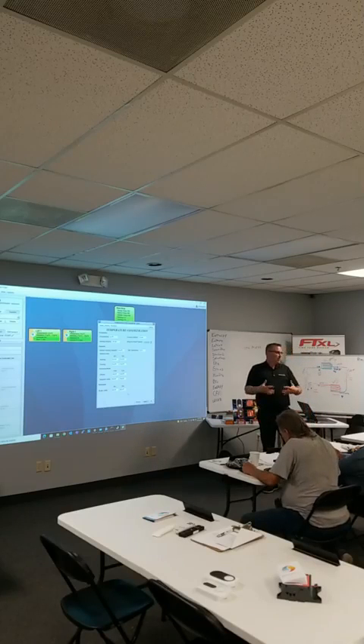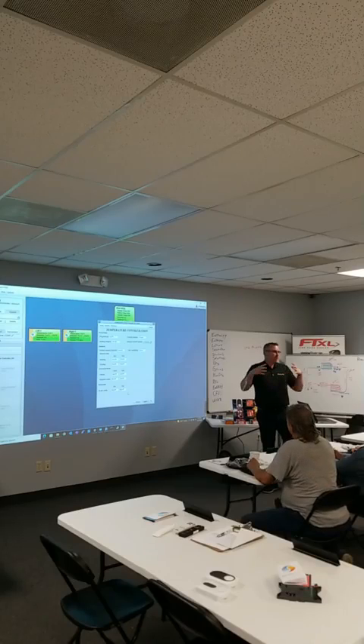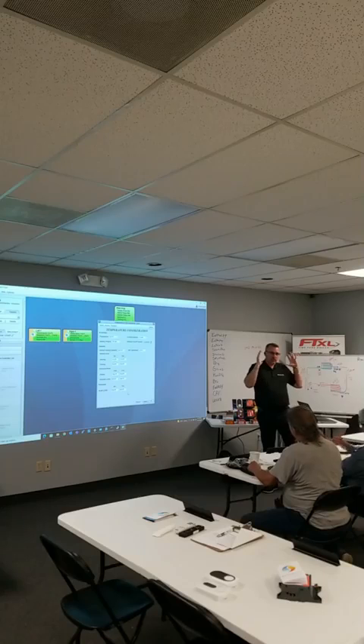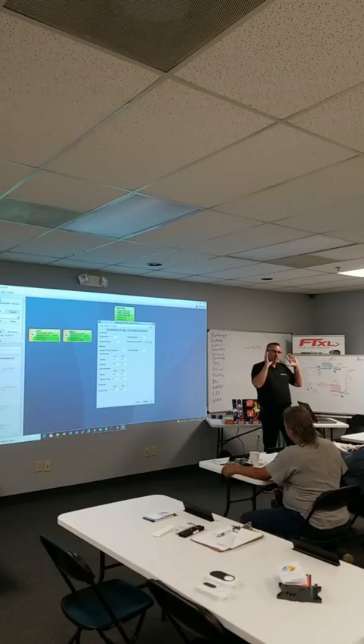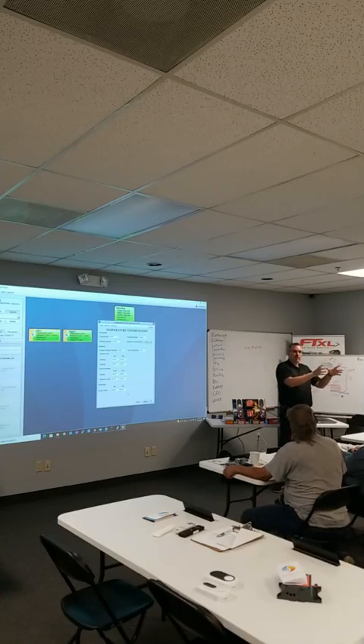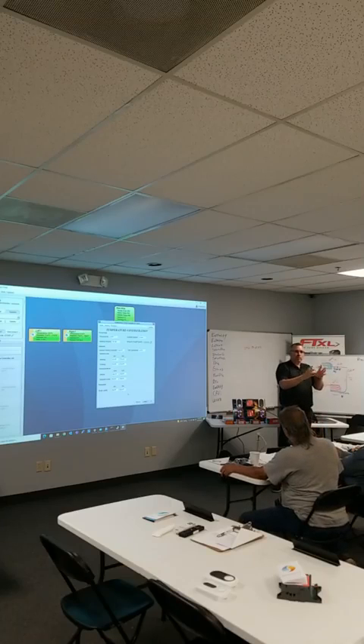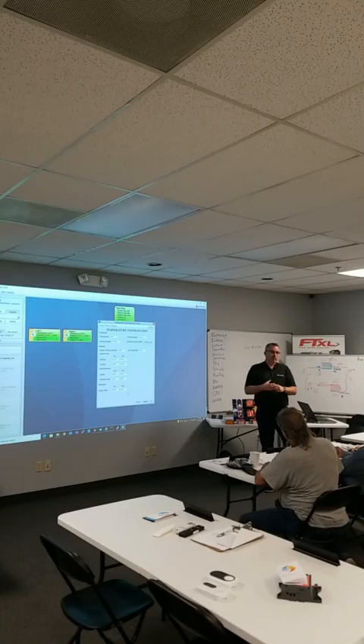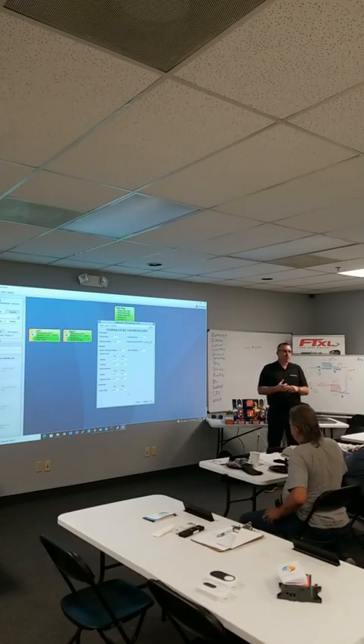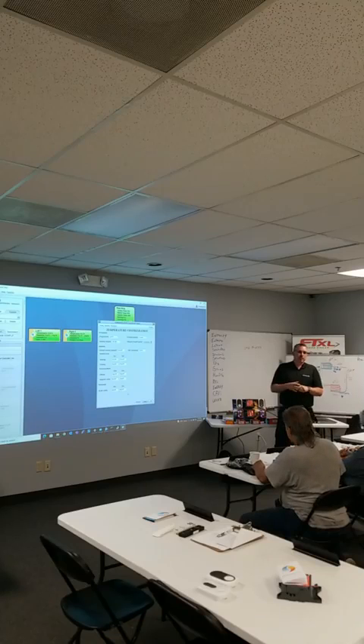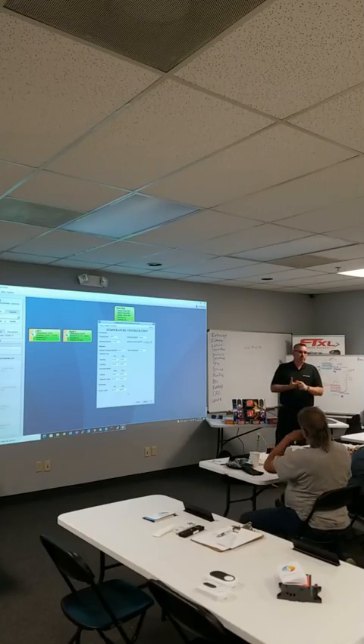So when you think about PROLON, it doesn't fit everywhere, but you have to think about it for light commercial. You're trying to solve a mechanical problem that you can control. If you buy a Wi-Fi stat, yeah, you can get it online, but can you change when the compressors start and stop on staging? No. You typically can't see discharge air either, unless maybe you buy a high-end one that shows discharge air and fan status.